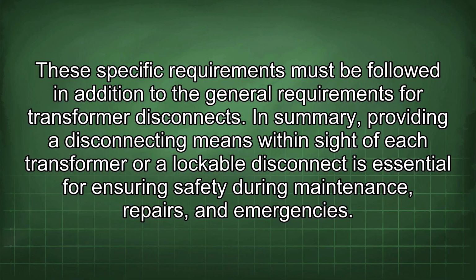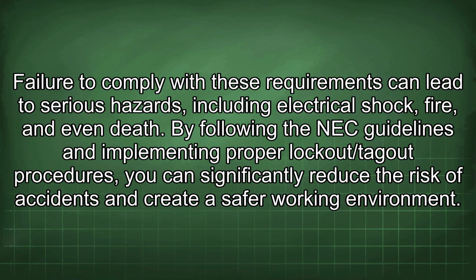In summary, providing a disconnecting means within sight of each transformer or a lockable disconnect is essential for ensuring safety during maintenance, repairs, and emergencies. Failure to comply with these requirements can lead to serious hazards, including electrical shock, fire, and even death. By following the NEC guidelines and implementing proper lockout/tagout procedures, you can significantly reduce the risk of accidents and create a safer working environment.